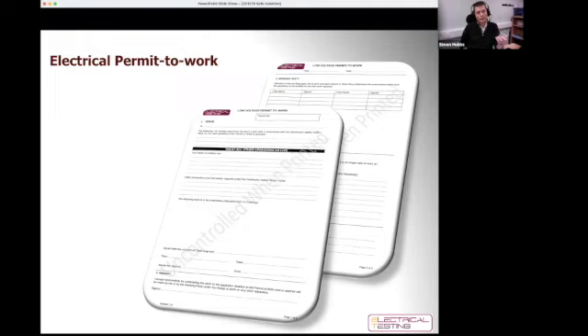But whilst we're isolating typically day to day on a low voltage installation with one supply, not necessarily required. I think as soon as you start to move to maybe two sources of supply, that's when we would start to look at an electrical permit to work.